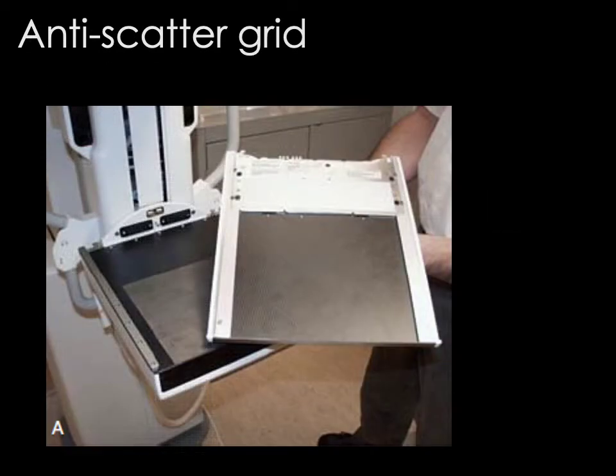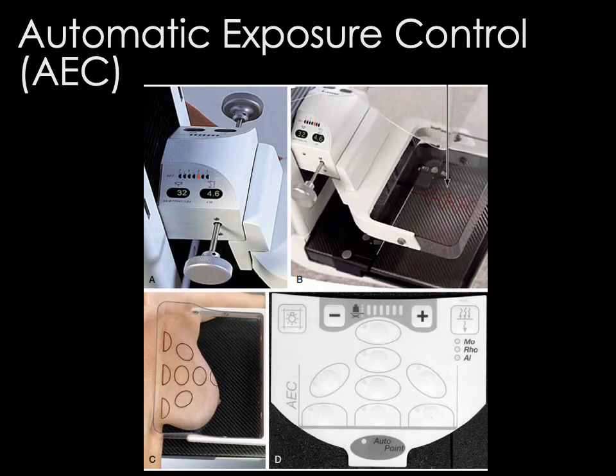Mammography also uses anti-scatter grids. The overwhelming majority of mammography is performed using automatic exposure control, or AEC. Similar to general radiography, there are multiple photocells above the image detector. These photocells measure the amount of radiation that reaches them and terminate the exposure when a certain dose to the photocells — and hence the detector — is reached.